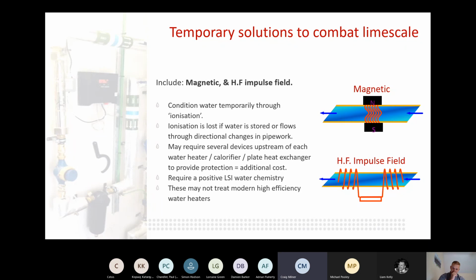Yeah, basically when you're doing design, you should check what the water chemistry is. A couple of manufacturers actually do a water analysis and then compare it to the long-term average on the site as well. So from the postcode, they'll find out who the water supplier is, Severn Trent, Thames, whoever, and they'll look at the long-term average, and then they'll look at the actual result that they took from the water quality test.